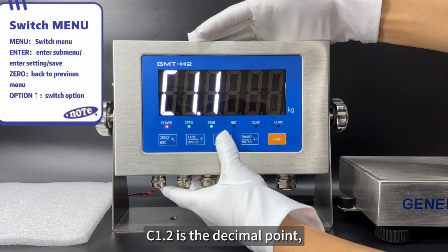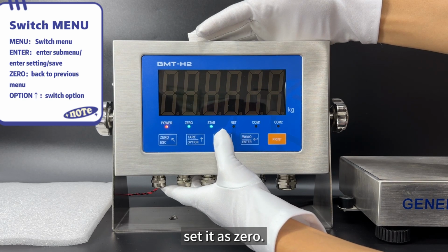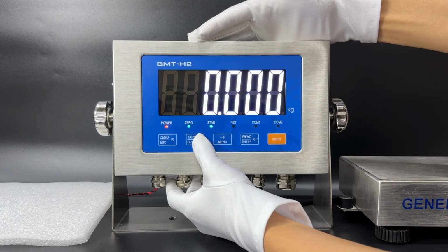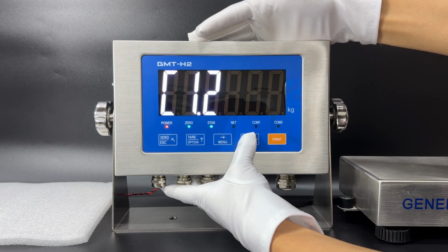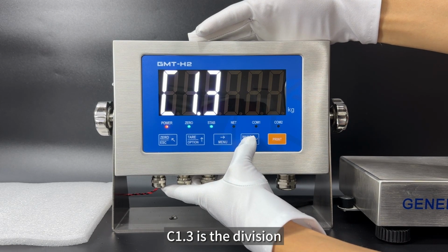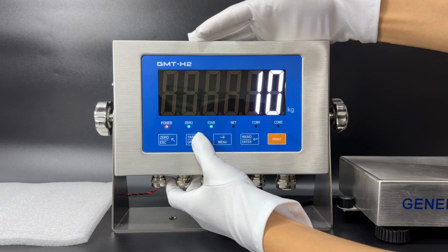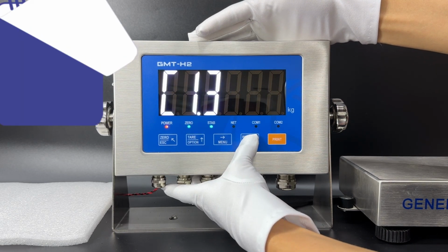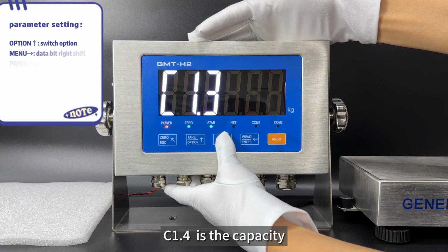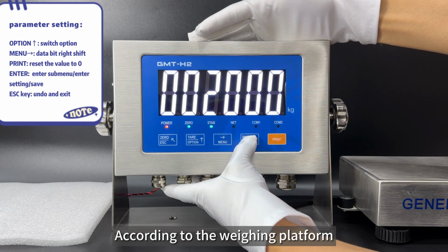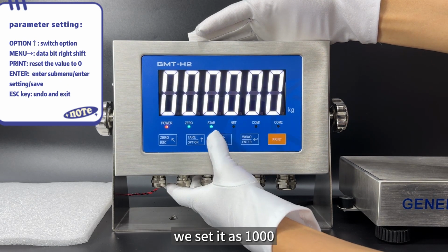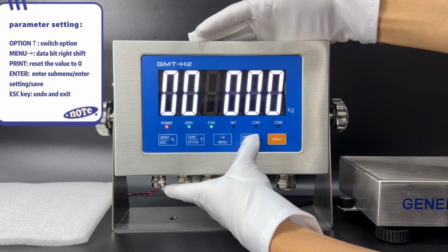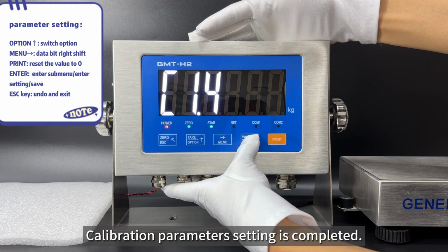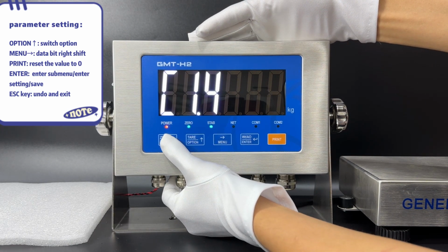C1.2 is the decimal point. Set it as 0. C1.3 is the division. Here we set it as 2. C1.4 is the capacity. According to the weighing platform, we set it as 1000. Calibration parameter setting is completed.